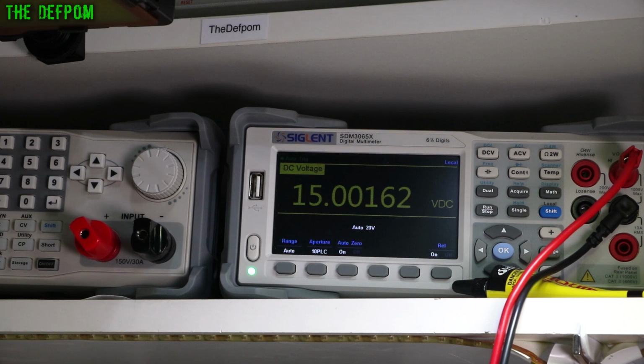So I've changed the test points over to the analog board, which are the other test points you actually do the calibration for, reference later on. Let me double check the voltages I'm supposed to be at. This one is drifting once I set it, which I think is just the adjustment itself settling. I'll double check the voltages while I'm waiting for that.